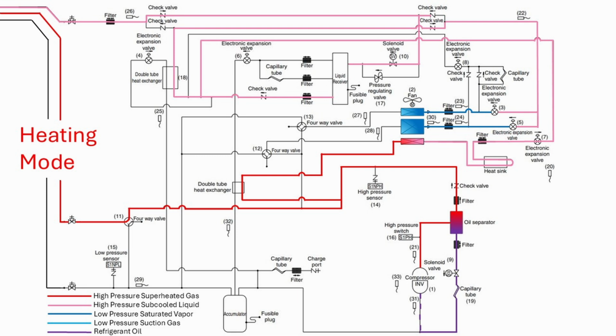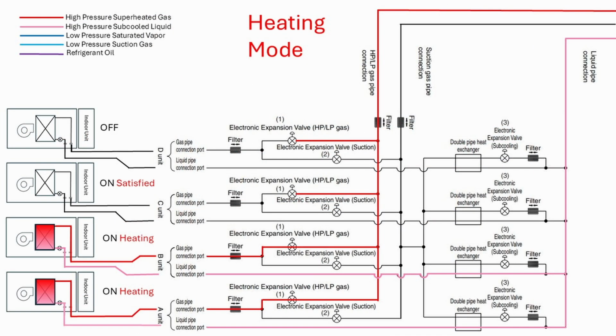As the refrigerant passes through the outdoor heat exchanger, it is absorbing heat from the outdoor air and changing the state of the refrigerant to a superheated suction gas. The suction gas leaving the outdoor heat exchanger is routed through two four-way valves to the suction line just ahead of the accumulator. The low-pressure gas then leaves the accumulator and travels back to the compressor to start this process over again. Here is an example of the same process through a multi-zone version of the branch selector box. You can see everything works exactly the same, except there is one selector box for multiple indoor units.